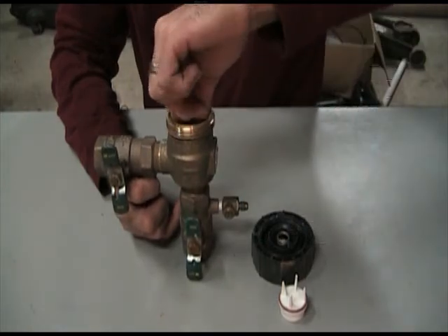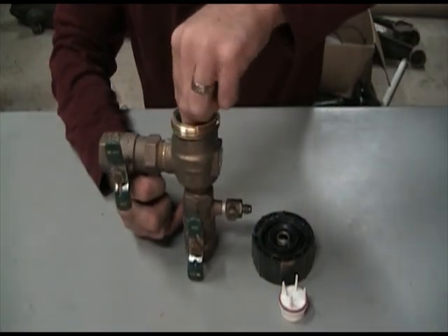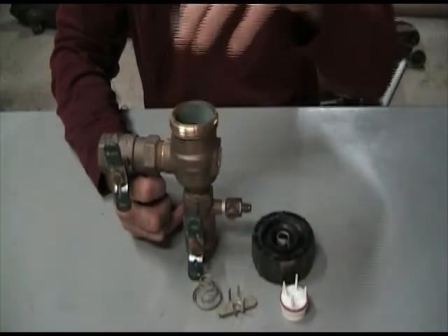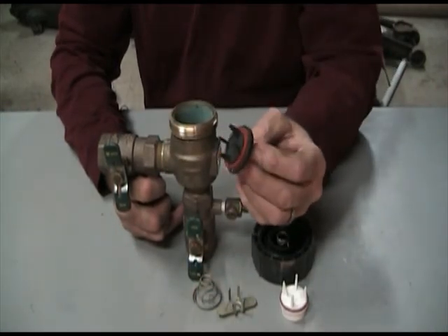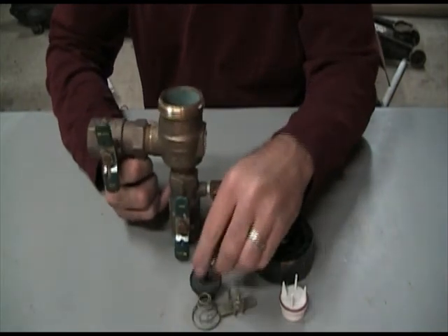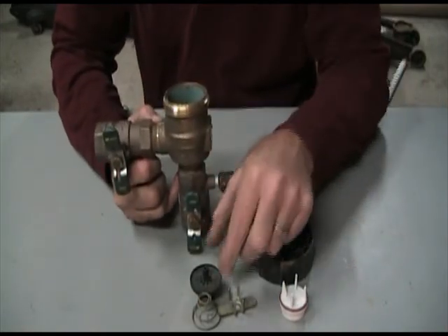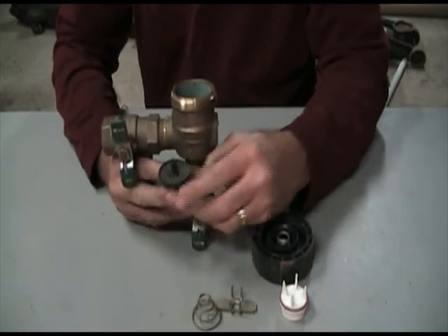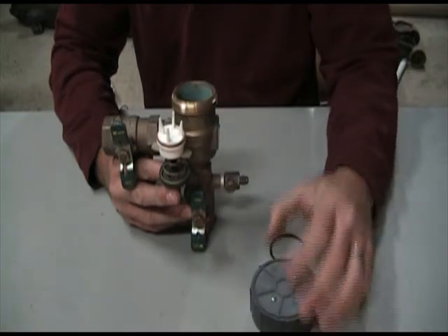And I snap this apart. You give it a quarter turn. A little metal retaining ring. Then a spring. And then another gasket. Okay? This basically, you have your seat inside here. Water comes up, pushes this up with the spring and the retainer, and this is here, and then your cap. This pushes this up into the cap to seal it.